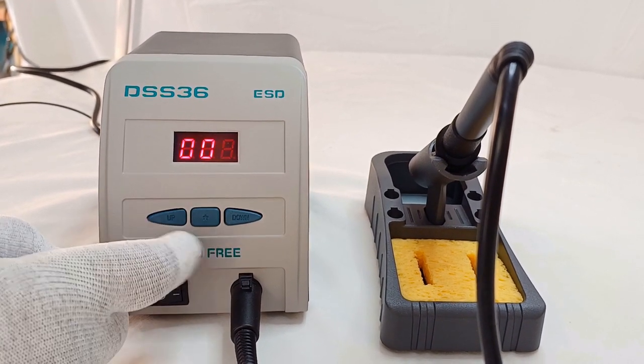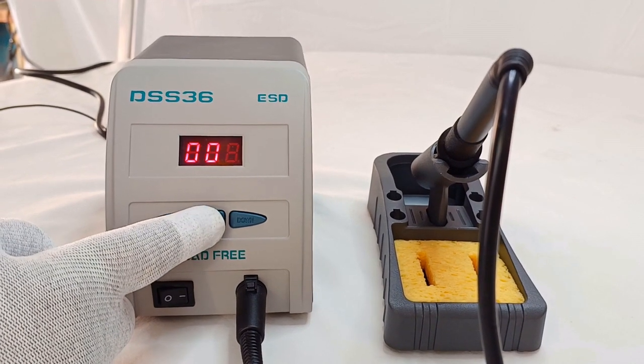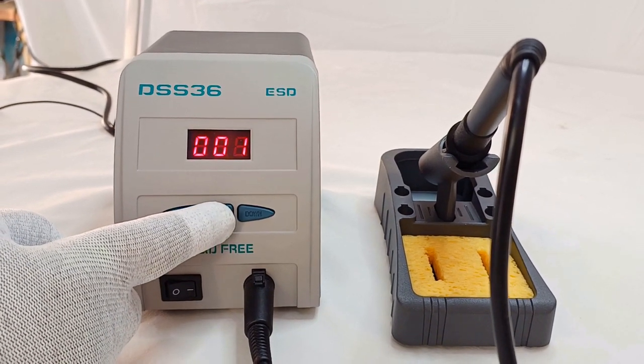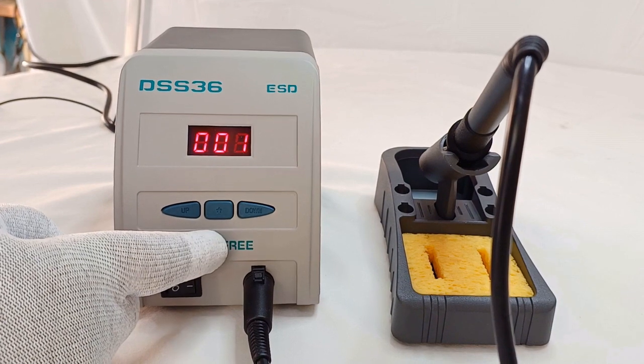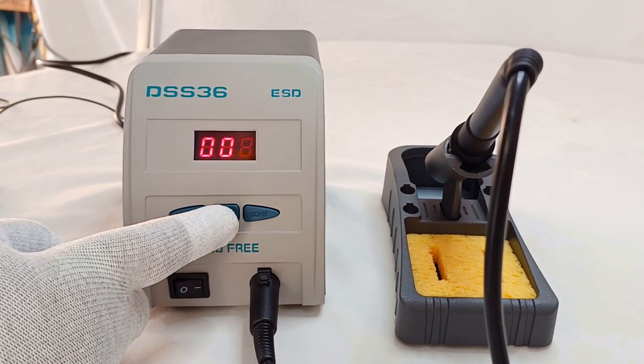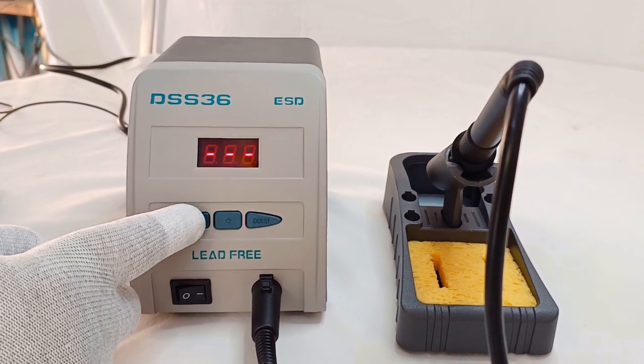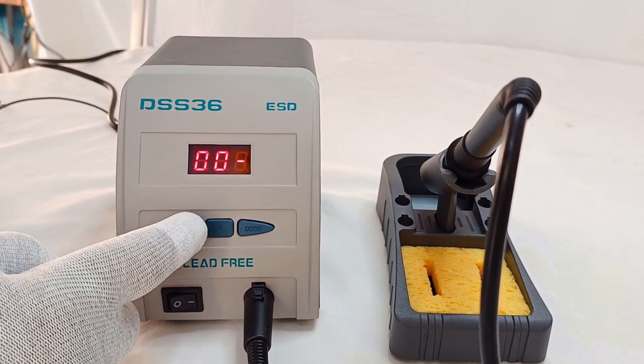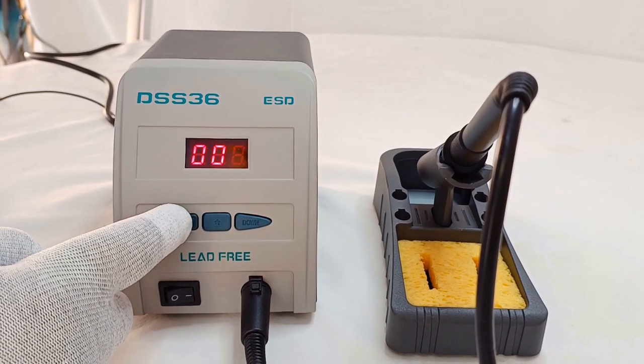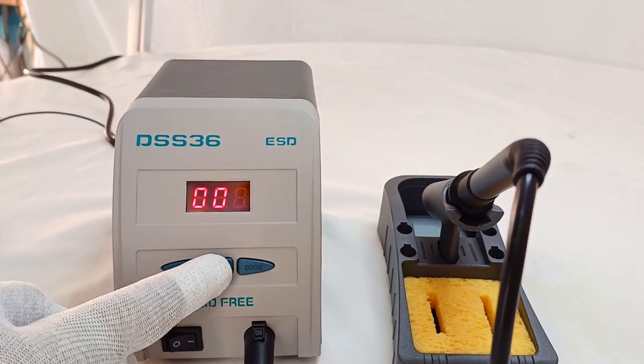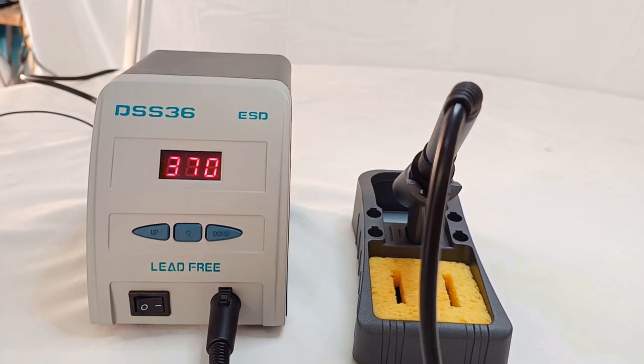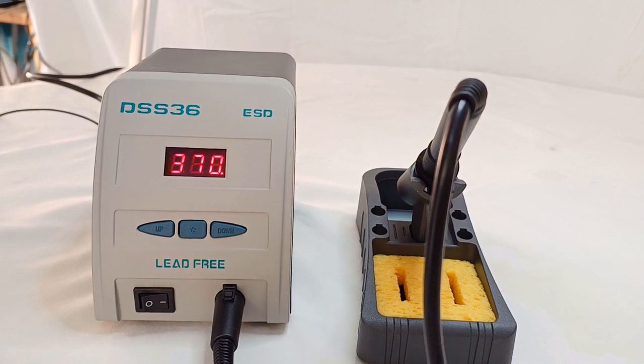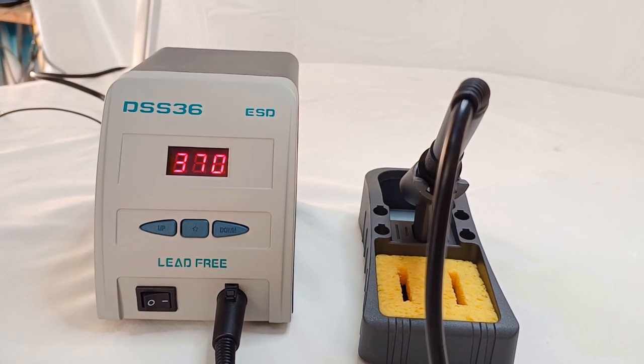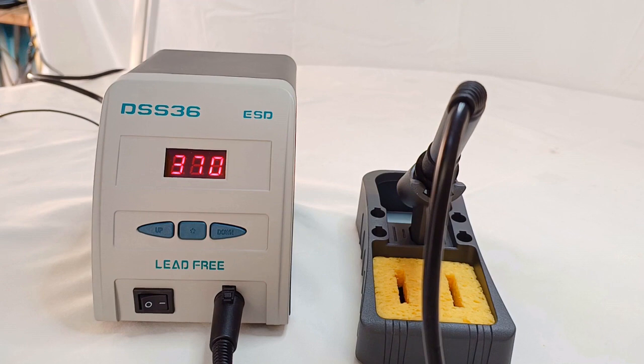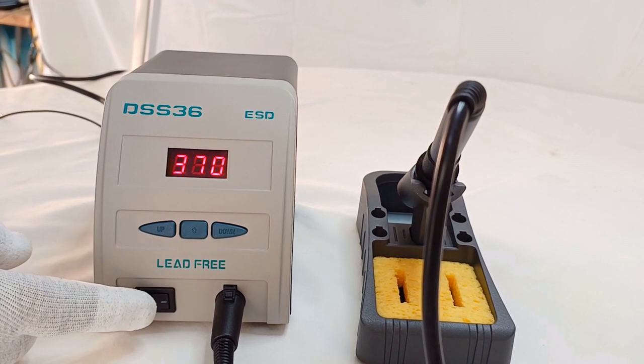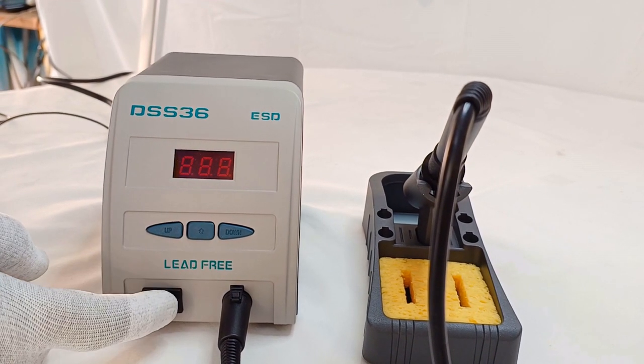Here we are using 001 as our new password, by using the star and up combination of keys, and press the star button. We have to repeat the process by pressing the up and star button combinations. We need to just input 001 and press the star button once again. We have changed the password from 000 to 001, and the temperature locking feature is not enabled yet. For enabling it, we need to switch the unit off once again and then switch it on.